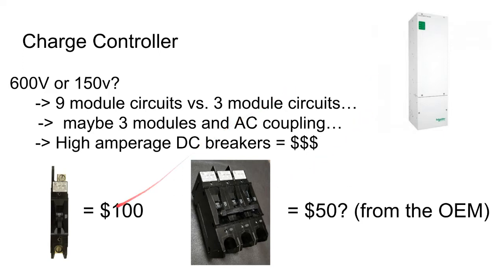But if you go and buy that specific single pole breaker, that's what everyone's looking for, and they charge accordingly for it. So what I learned from that lesson is that DC breakers, you want to buy ahead of the rest of the project. As soon as you know the breaker sizes, start pricing them out, because you can find some really good deals on them. That's the one item that might not be worth buying with the rest of the system.